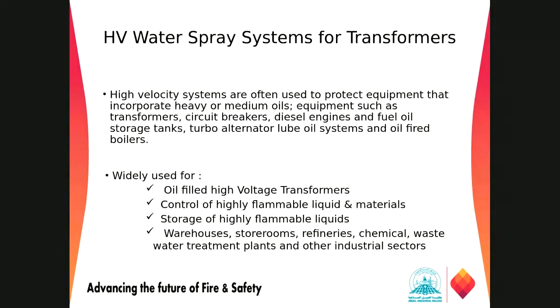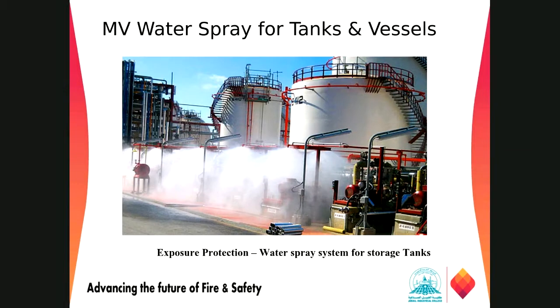And it also covers the pumps themselves. Yes, it covers the pumps also, but not the fire pumps. Now we are talking about everything for the process industries. Our fire pumps should be, according to guidelines from the process industry or from UL, FM, or oil industry guidelines, at least around 70 to 80 meters from the process area. And they are protected as we discussed, by a sprinkler system for group 2 hazard occupancies.